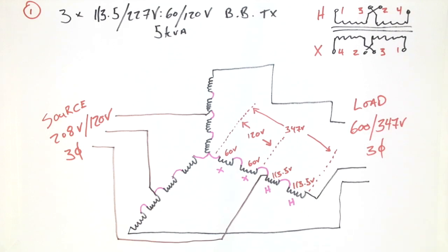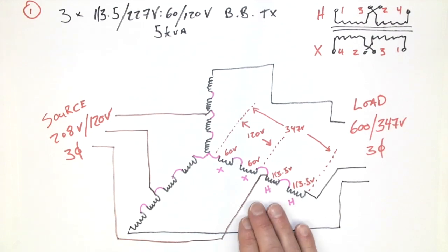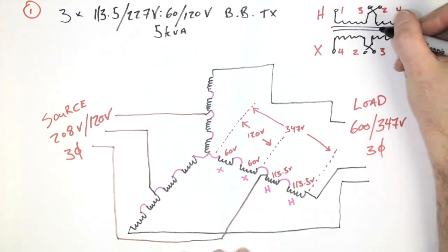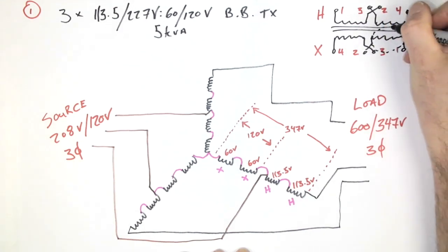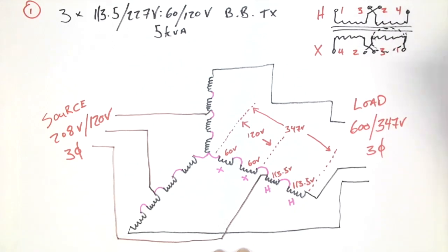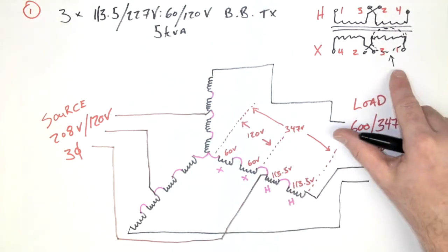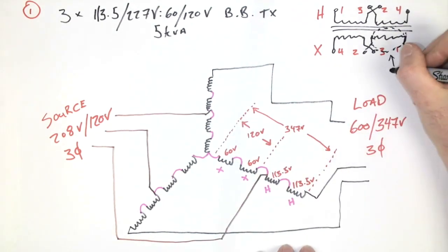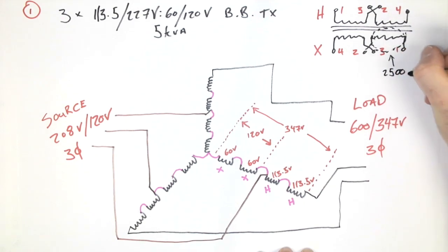Now, after we've got the configuration completed, we need to know what is the maximum kVA that this particular bank can supply. And at this point, we need to have a firm understanding of what the kVA value will be of each winding of the transformer. So I'm going to look at one winding of the transformer here. One winding, we said at the beginning of the presentation, is going to be equivalent to half of the total kVA rating of the transformer. So if the transformer is rated 5 kVA, it means that one winding is rated 2500 VA or 2.5 kVA.